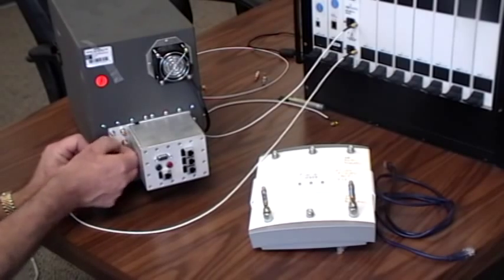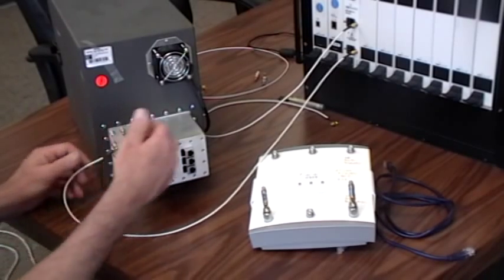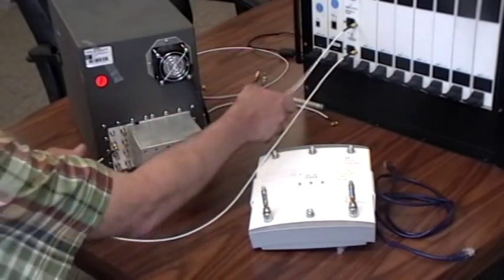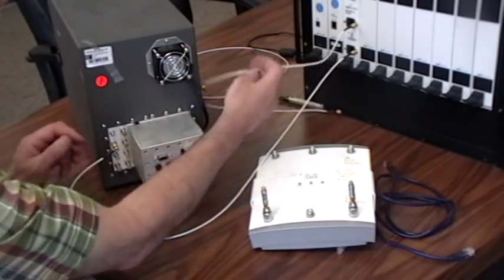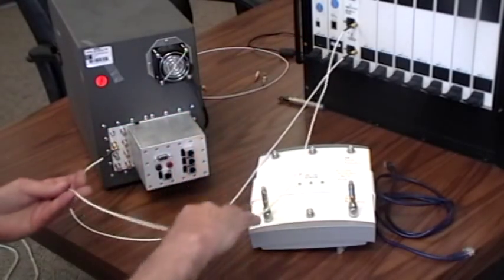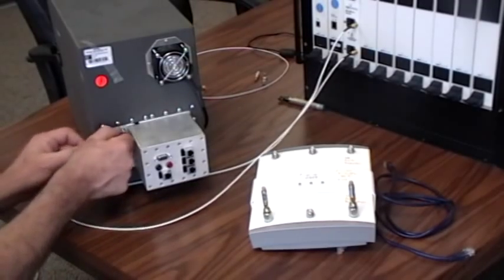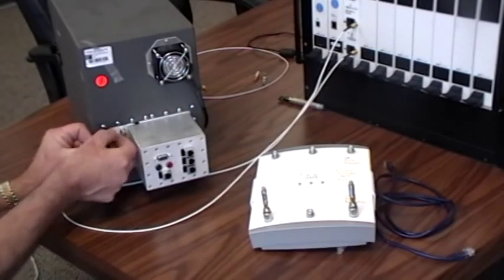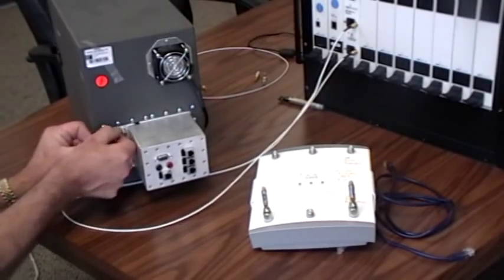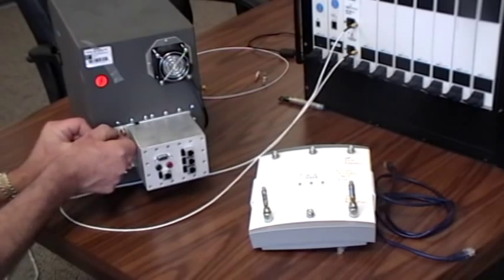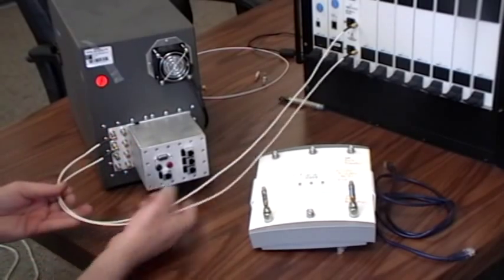With RF cables, you just want them to be tight and you want them to have no kinks. You want the bends to be gentle and just well managed. No tight curves and no stress on the cable. That keeps them working for a long period of time.